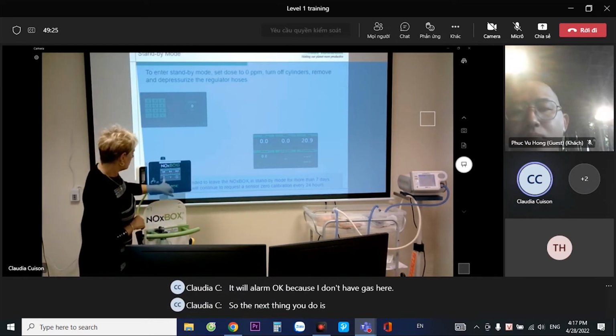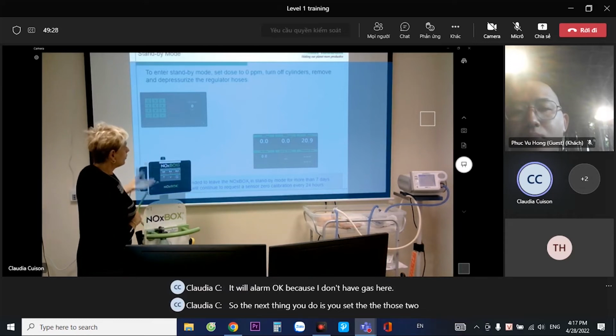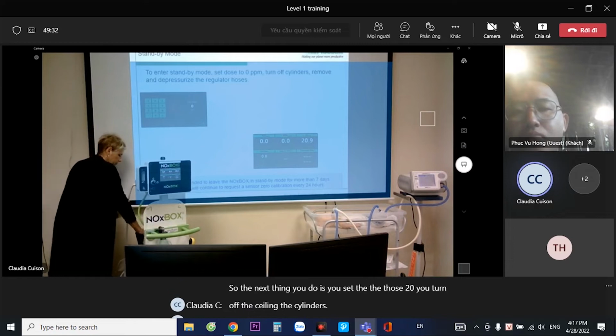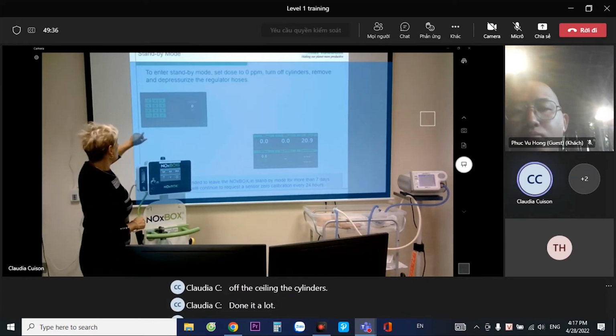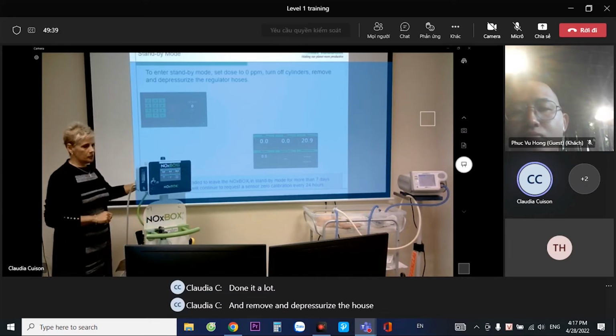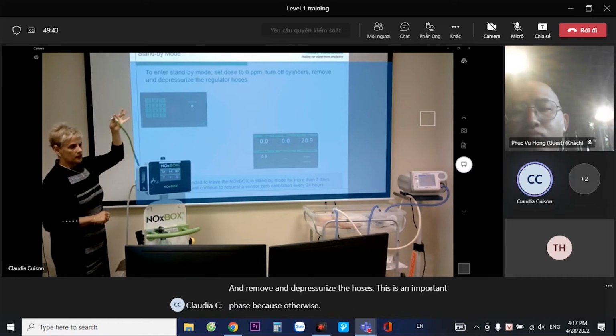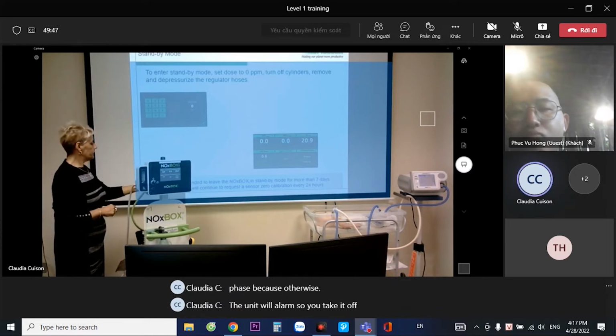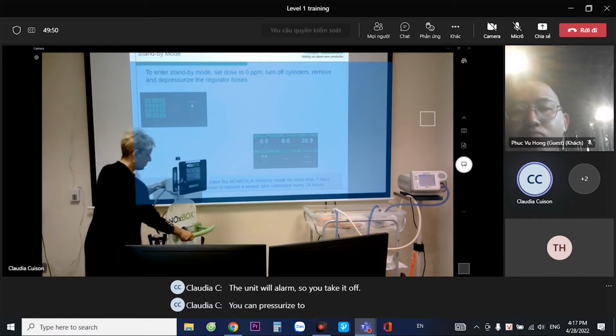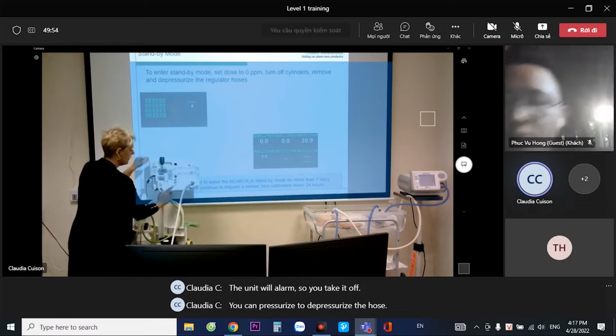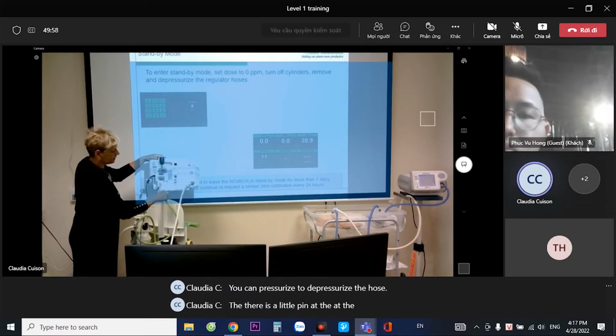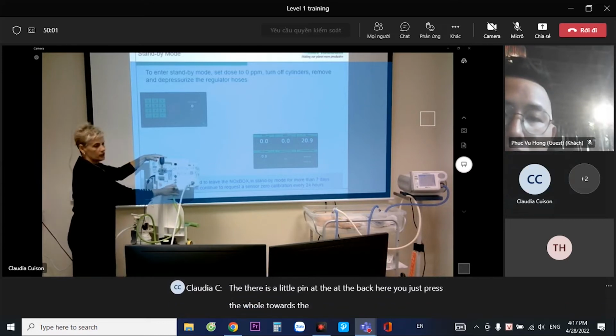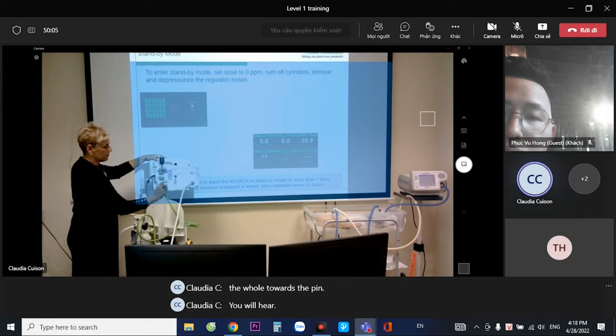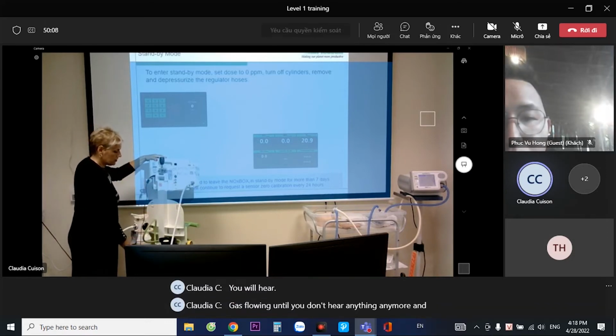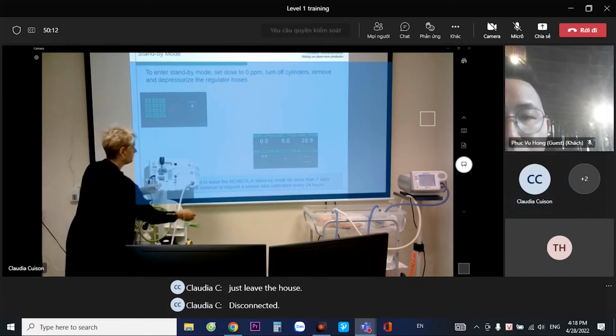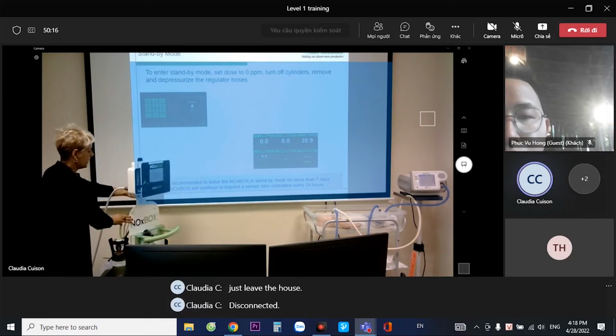So the next thing you do, as you set the dose to 0, you turn off the cylinders, turn it all off, and remove and depressurize the hoses. This is an important phase because otherwise the unit will alarm. So you take it off, you depressurize. To depressurize the hose, there is a little pin at the back here. You just press the hose towards the pin. You will hear the gas flowing until you don't hear anything anymore, and you just leave the hose disconnected at the back.